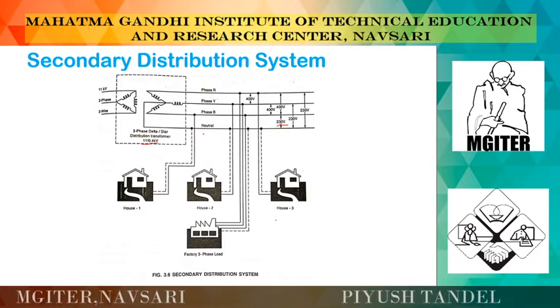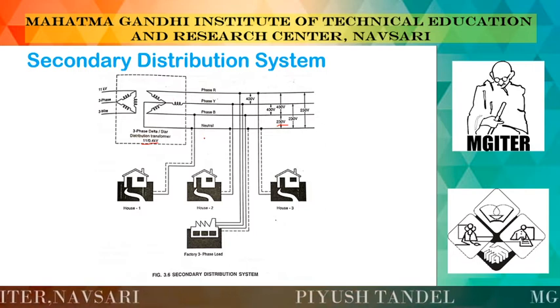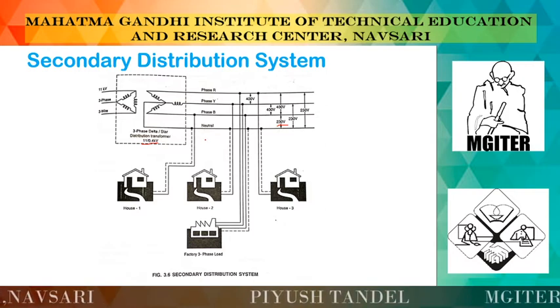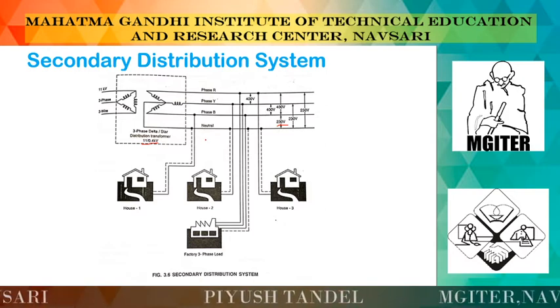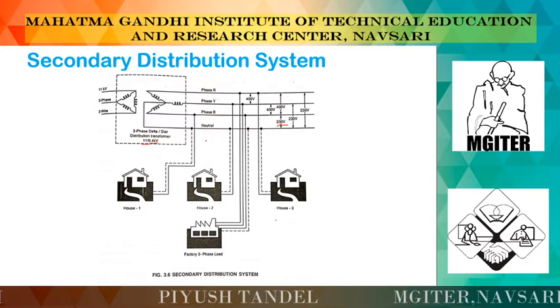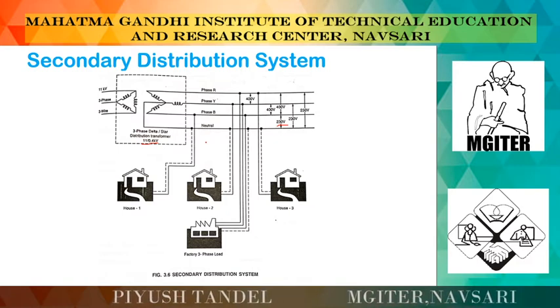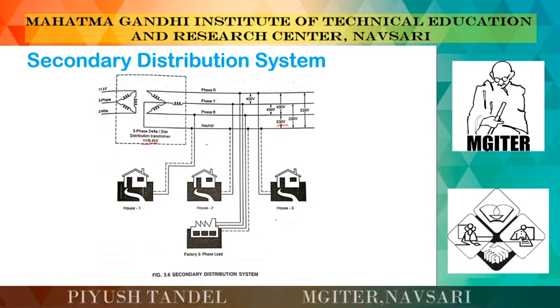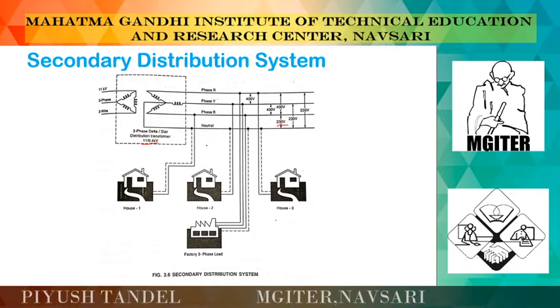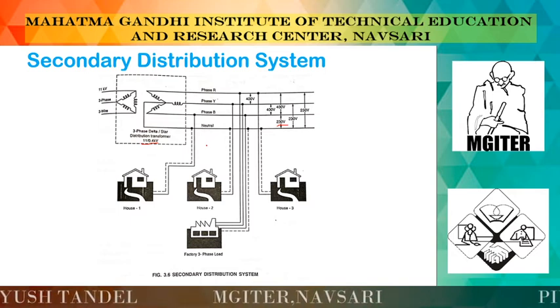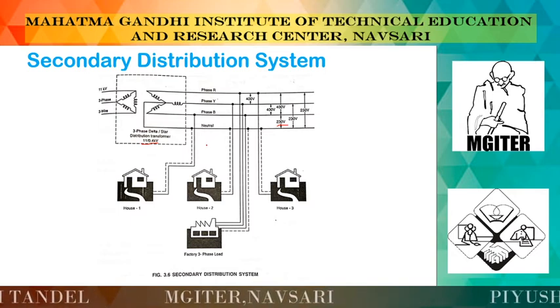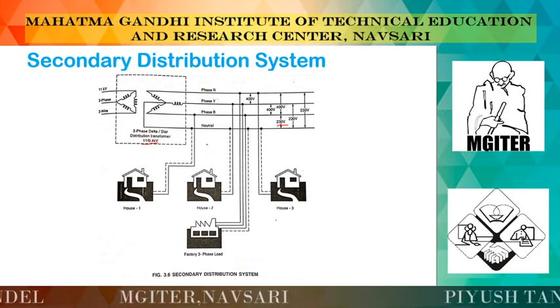So for the secondary distribution system we have the system of three phase four wire, where the neutral is also considered. A typical secondary distribution system is shown: the primary distributor delivers power to the distribution substation, where the three phase delta star distribution transformer steps down the voltage level from 11 kV to 400 volt. The low voltage secondary, that is single phase domestic load, is connected in between one phase and one neutral.